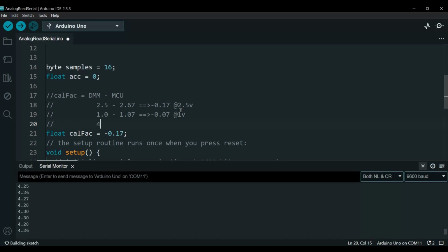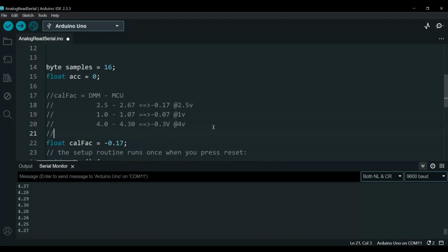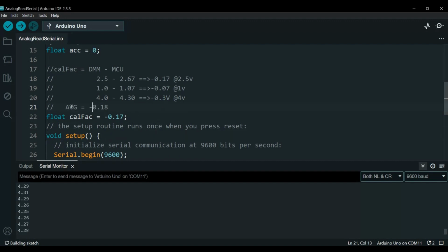So at 4 volts, the DMM reading is 4.00 or 4.0, whatever, minus our MCU reading, which is 4.253, let's say 4.30. So from that, we can see the difference is about 0.3 volts. Then I'll take the average of these three. Okay, this is at 4 volts. So the average is about 0.18, which is minus for sure. So here we go. We will take the average as the calibration factor, so 0.18.